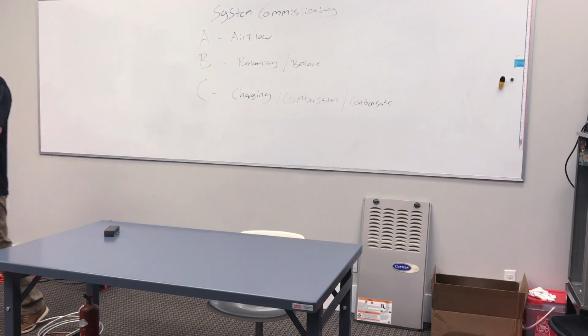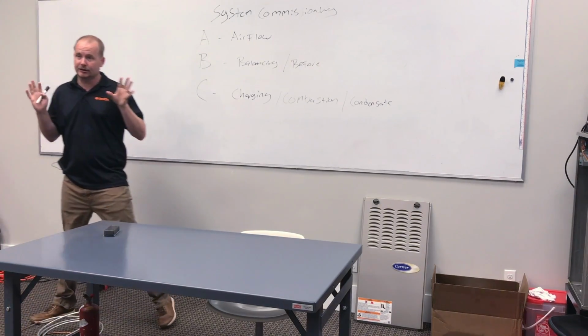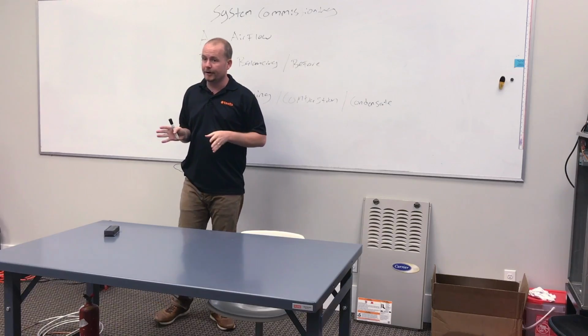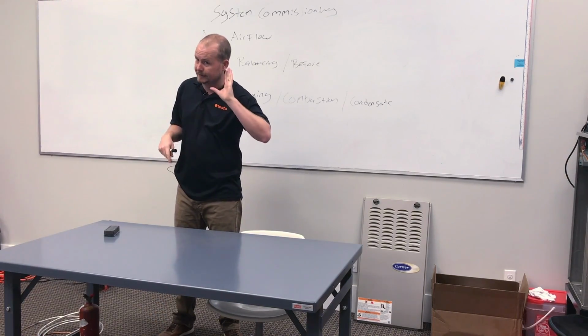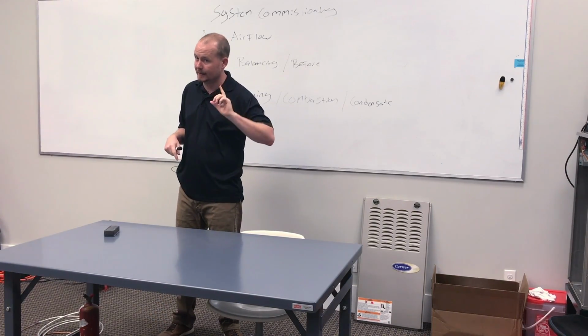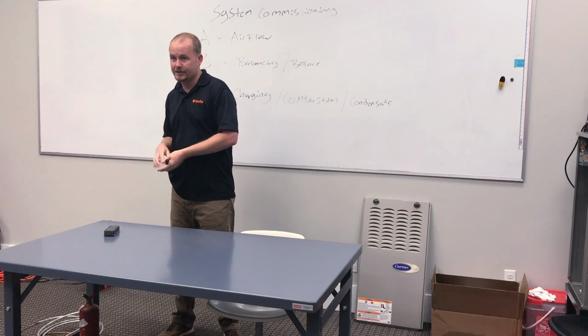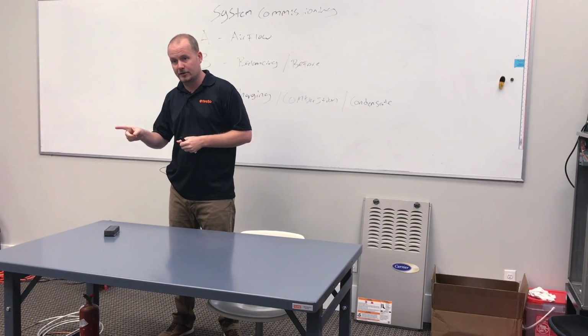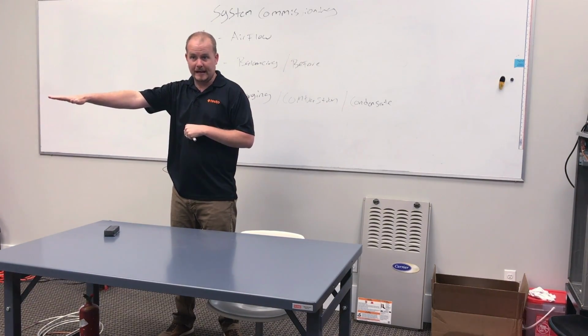And so installers, I'm not just saying this, this is legitimate. This is what I want you to do. You start a unit up, start up the blower first, listen, is it running? Does it sound like it's coming up to speed? Is it set on high speed? Great. Now you go to the condenser, you put in that disconnect, you're listening. Compressor running, condenser fan putting heat out the top.